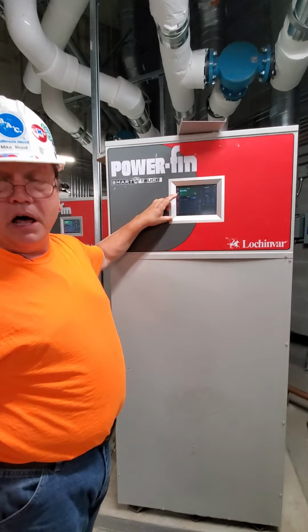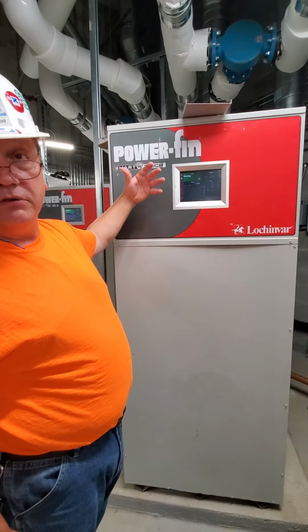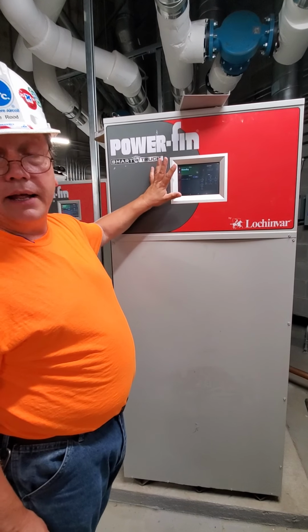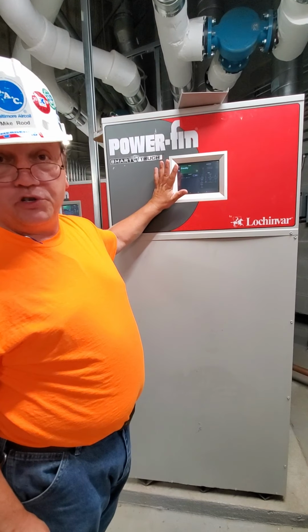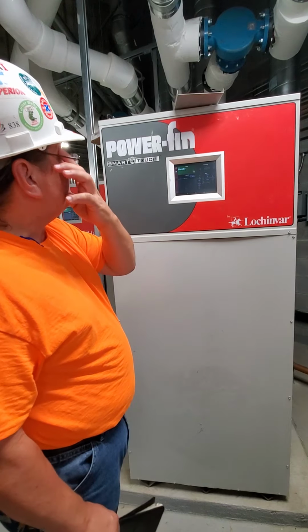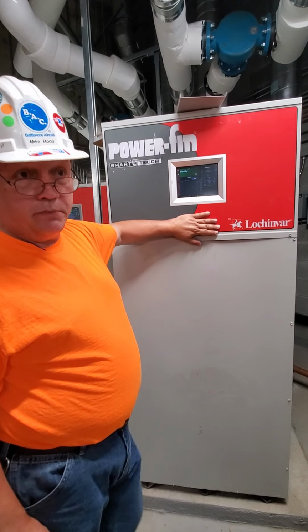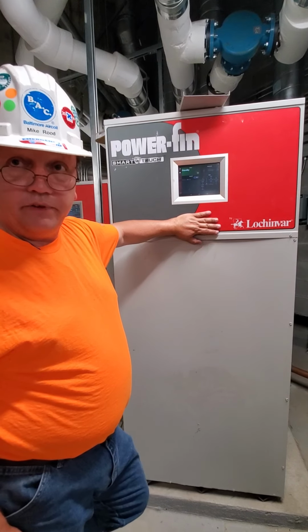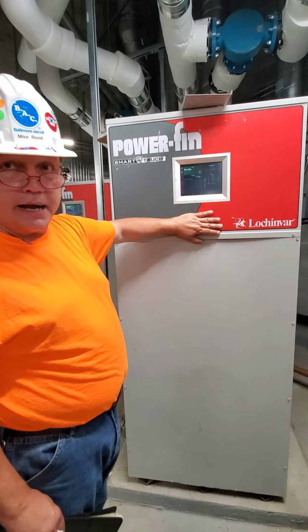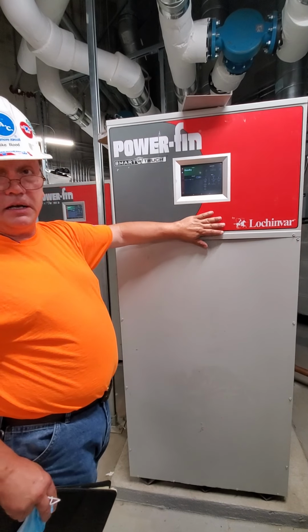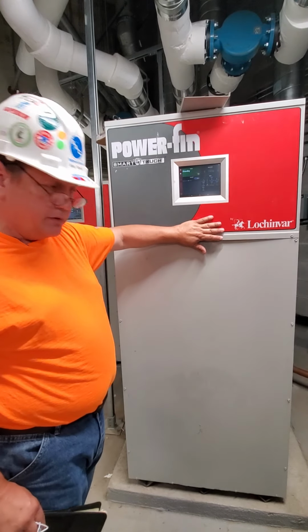There's a multitude of lockouts in the service manual that will tell you what that lockout is and what the common solutions are to remedy the problem. The burner on these should be removed and cleaned once a year. It is a cloth mesh type burner. It does need to be cleaned periodically. Once a year is minimum.